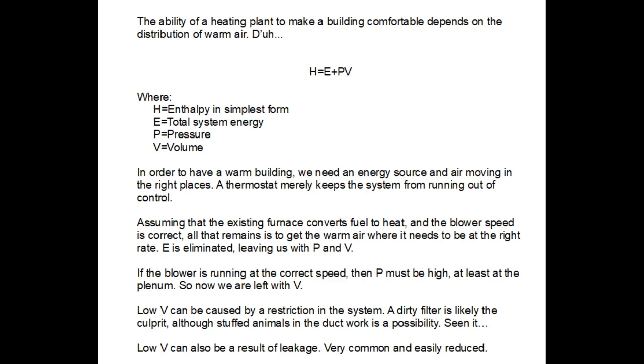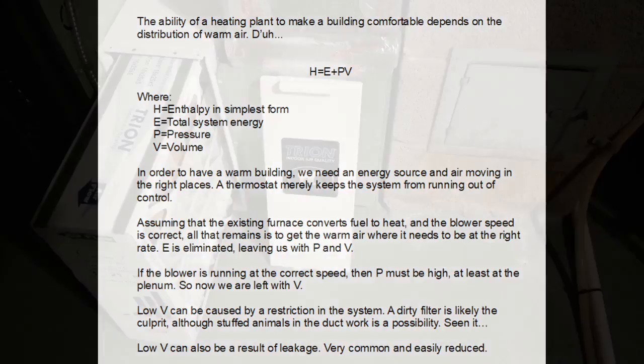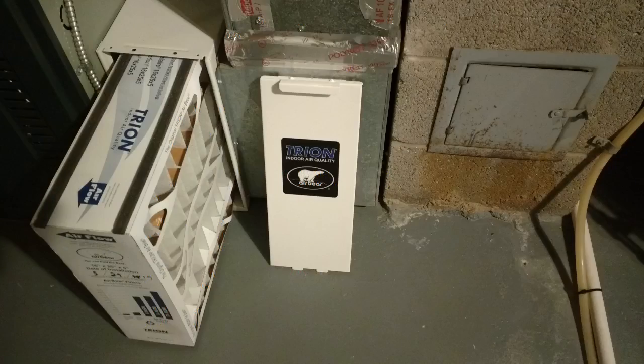So we have to check the blower. Is the blower running? If it is, then we must have pressure, at least at the plenum. But that doesn't mean we have volume. Volume may be a problem if the system is restricted. Now, restrictions can come from a couple of different sources. One is perhaps a dirty air filter, or one with too high a MERV rating for your system. I use a MERV 8. One way to tell is to pull the filter out and see if the airflow increases substantially.